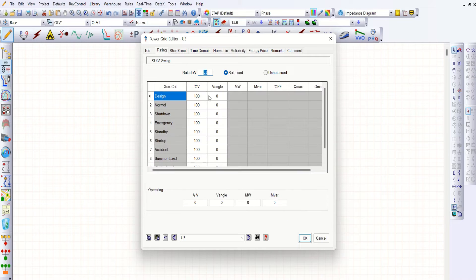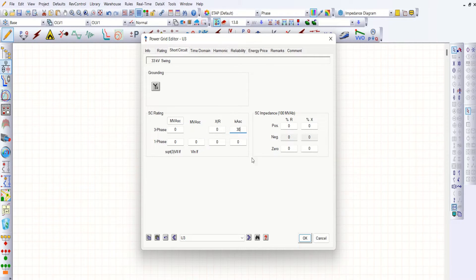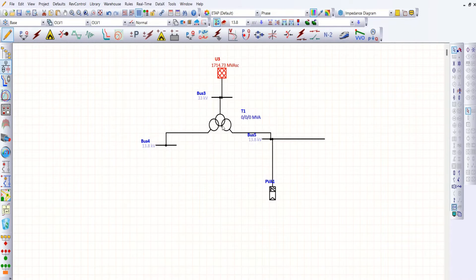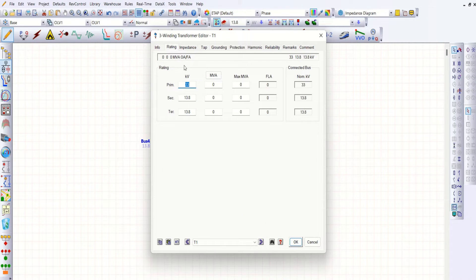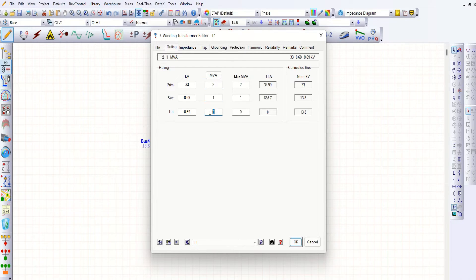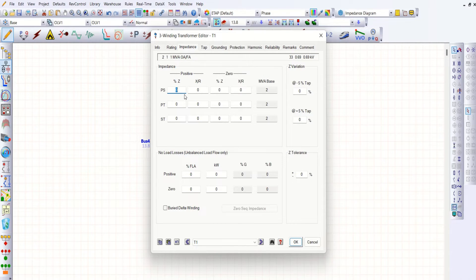This is a 33kV system. Let's take a short circuit current of 30kA. X/R ratio is 14. Here you may have 33kV / 0.690kV both on the secondary as well as tertiary winding. This is around 2 MVA — let me say 1 MVA in each secondary and tertiary winding. In impedance, you can take 5% between primary and secondary, 5% between primary and tertiary, and 10% between secondary and tertiary. X/R ratio — let me stick to 10 in all three cases.